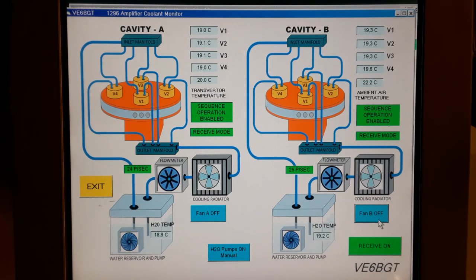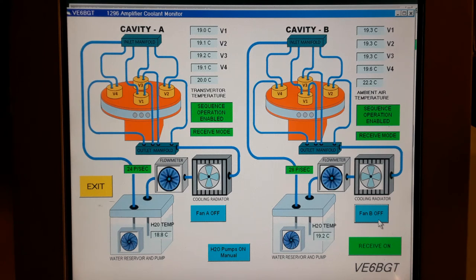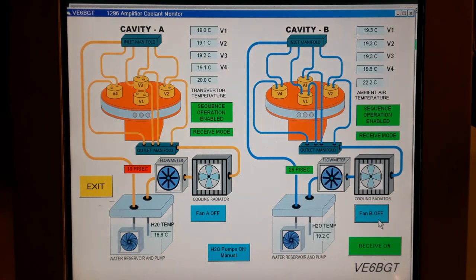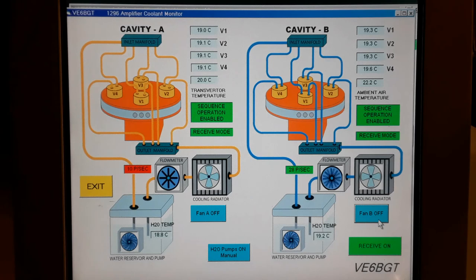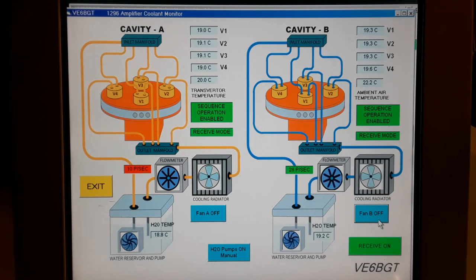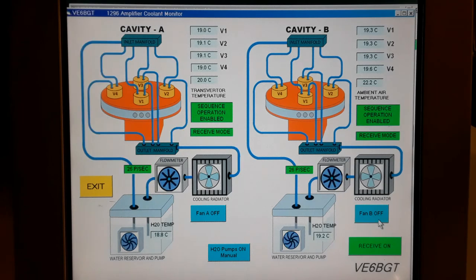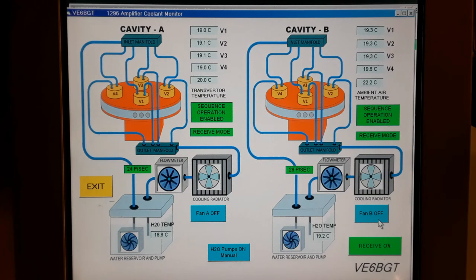The water lines are right now indicating blue, which means there's good coolant flow. To simulate a flow problem, I just pinched off one of the ball valves from a water tank. You'll notice the water lines have changed from blue to orange, and the pulse rate from the flow meter has dropped down below 10 and turned red. I once again open the valve and the flow's been restored and everything's back to normal.